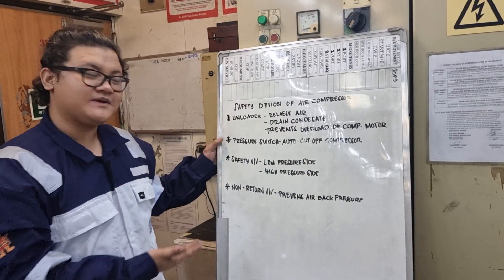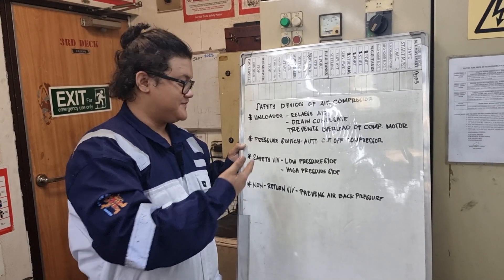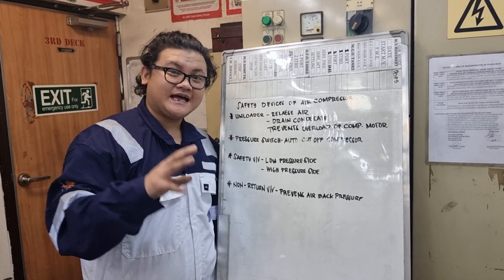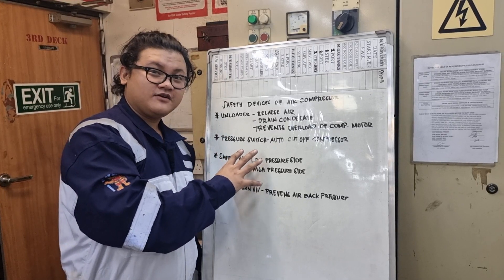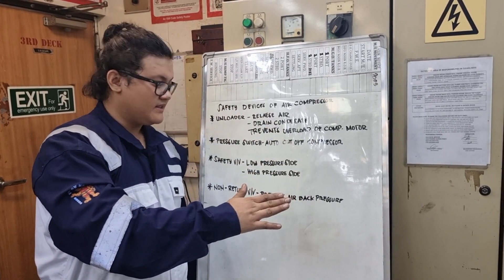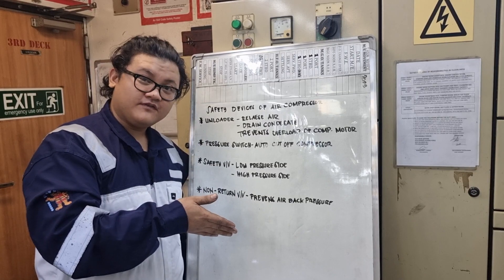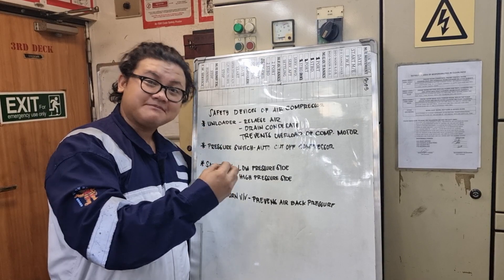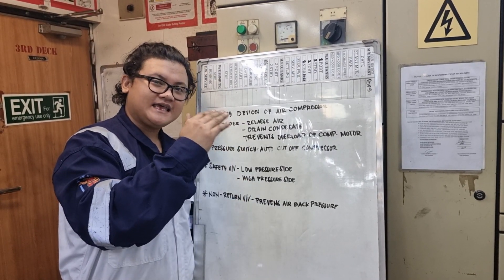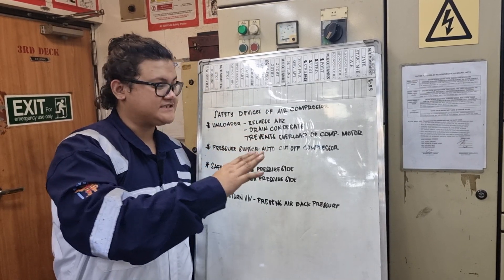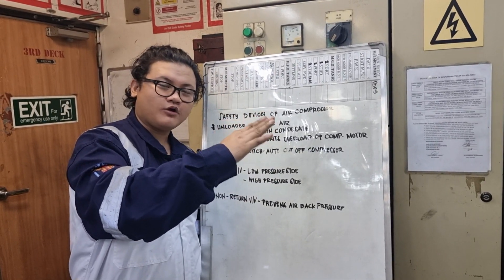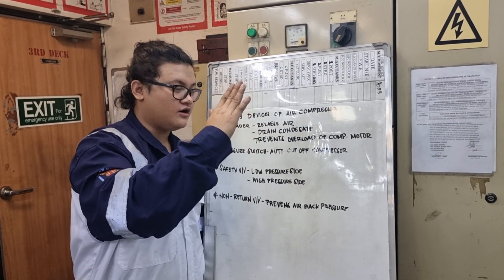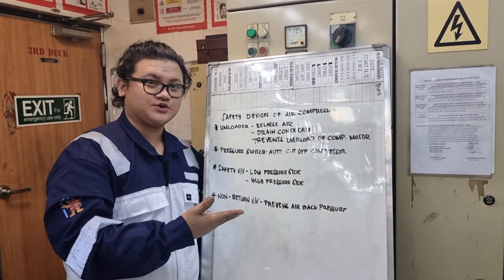Now, let's proceed with the second one: pressure switch. Pressure switch is attached to the air bottle that is receiving the air from the compressor. It automatically cuts off the supply from the compressor motor, or automatically stops the compressor motor, once it attains the desired air pressure. For example, you set it at 3 bar or 4 bar. Once you reach that pressure, it will automatically turn off the compressor motor.